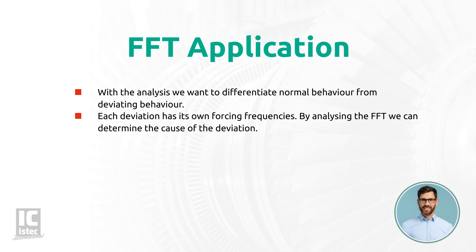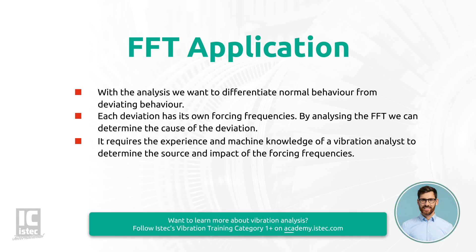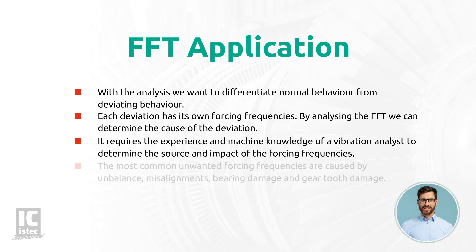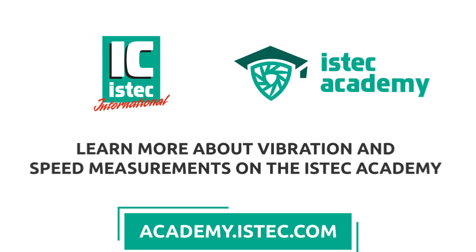Even though some standard forcing frequencies are described in the literature, it requires the experience and machine knowledge of a vibration analyst to determine the source and impact of the forcing frequencies. As mentioned in the first module, the most common unwanted forcing frequencies are caused by unbalance, misalignments, bearing damage, and gear tooth damage.